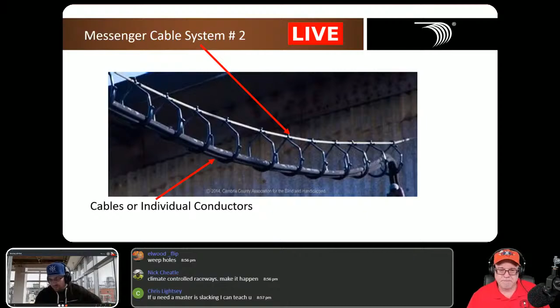Okay. Next. Item 9, Jay, hazardous classified locations were specifically permitted by other articles in the code. So MC cable can be used in Class 1, Class 2, or Class 3, Division 1, and Division 2 with certain caveats. For example, interlocked wouldn't be allowed in a Class 1, Division 1, for example, or even 2. But it might allow smooth or corrugated to be used, because remember, we're talking about MC in general. It just so happens that the most frequently used is interlocked. But you still have the smooth, which is called continuous because it's a continuous extrusion. It's kind of like a tube, if you will. And then you have corrugated, which comes out very similar, but it's a welded tape.